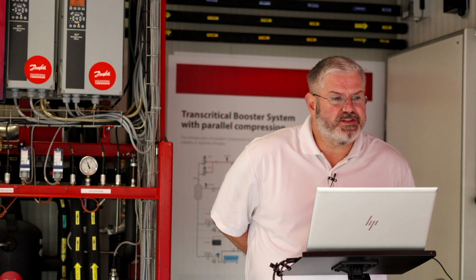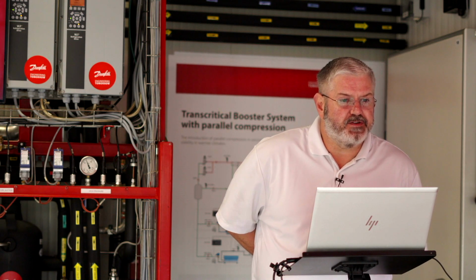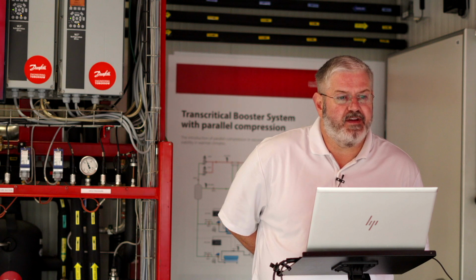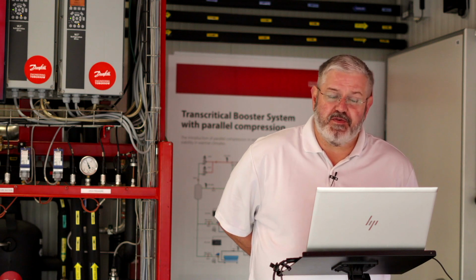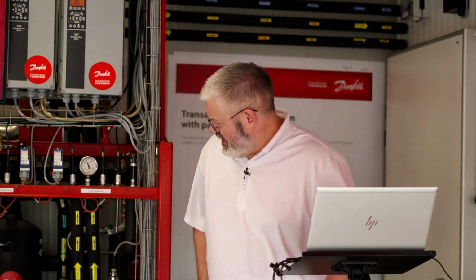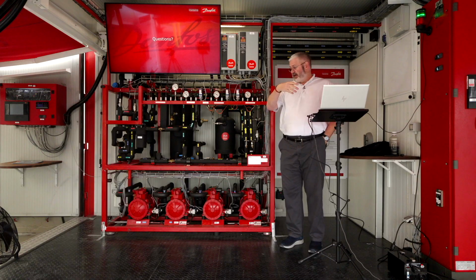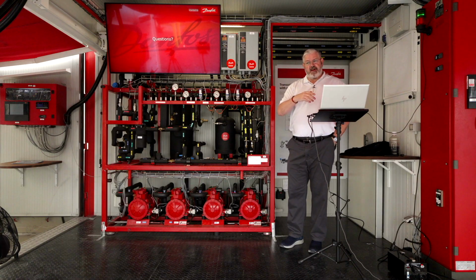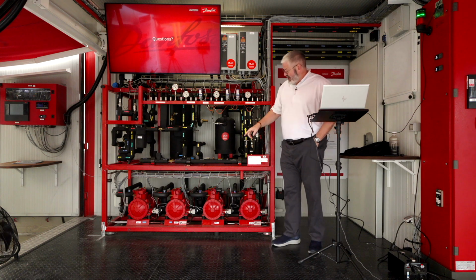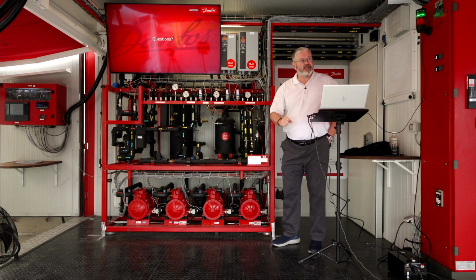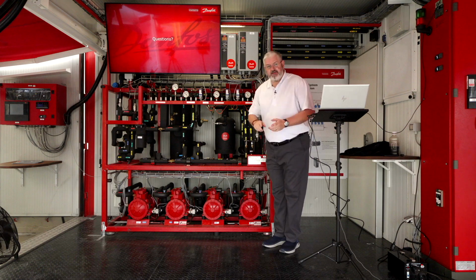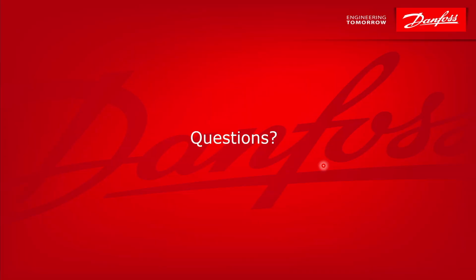Okay, we've got a question that says, so typical system customers run receivers at minimal capacity, CO2 charges at 100%. So CO2 actually, it doesn't charge to 100%. We charge the liquid line out to the store, feeding all of our evaporators to 100%. But can I go a close-up real quick, Josh? So to answer that question, back to our receiver here, again, flash tank and receiver are called the same thing.